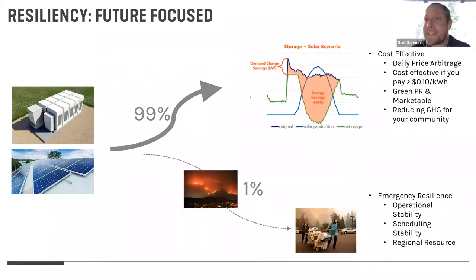Why? It's expensive. Unless you're on an island off of Alaska, running a generator and buying its fuel is going to be far more expensive than purchasing power from the grid. But if the grid's not there, you've got your generator. The other issue with generators is maintenance and the test run you have to do every month, depending on your jurisdiction, to make sure it's up to snuff. So when we're looking at battery and PV systems, we're trying to find a solution to avoid a generator if we can. Now, there are some cases where code requires a generator, such as hospitals for emergency power.